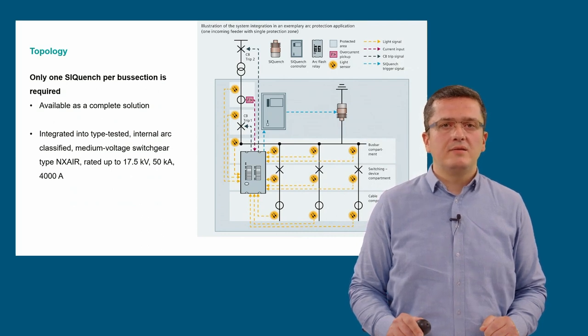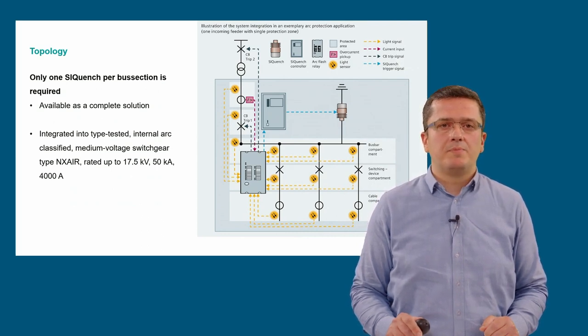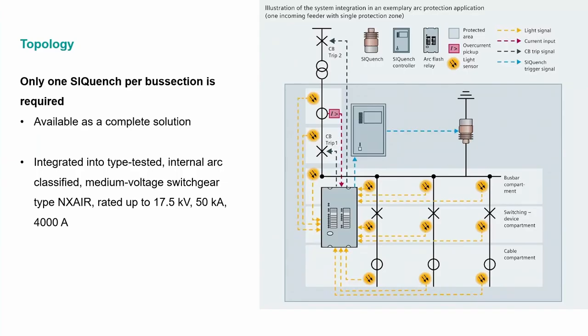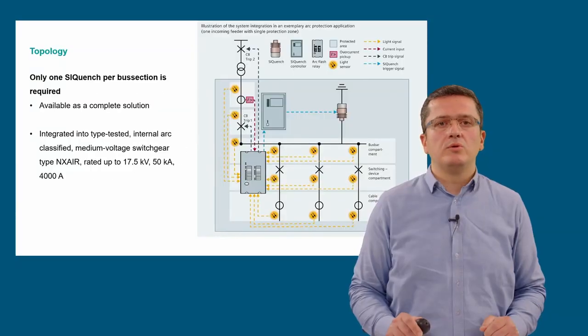SIQuench is located as fixed mounted in the bus bar compartment. That is why only a single SIQuench per bus section is required and enough for the protection. As of today, SIQuench is available as a complete integrated solution into the internally classified air-insulated medium voltage switchgear type NXAIR up to and including 17.5 kV and 50 kA.